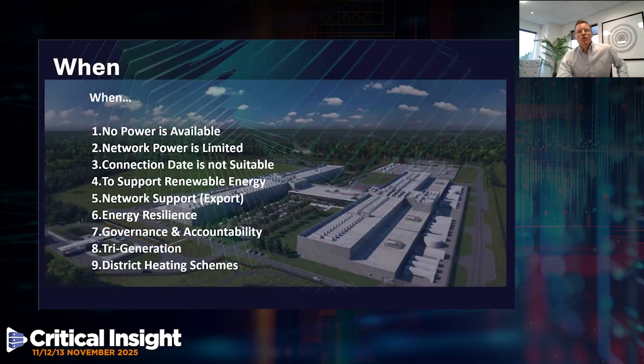So when would you need a microgrid? Just listening to the last talk about sovereign AI and all this sort of good stuff - all of these facilities require power. So if the network's not available to give power, you could use a microgrid. If the network power is limited, so for instance you want 100 MVA but you can only get 10 MVA, you can use a microgrid connected in parallel with the grid.